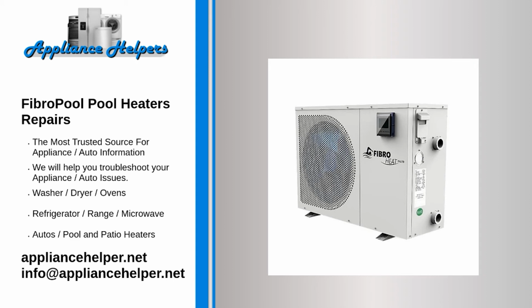Enough refrigerant. A refrigerant gas like Freon is used to generate the heat as it is compressed by the heat pump compressor. Although not common, over time small amounts of the gas can leak out. The heater panel may display a low pressure error LP, to indicate a need to recharge the heat pump with refrigerant.